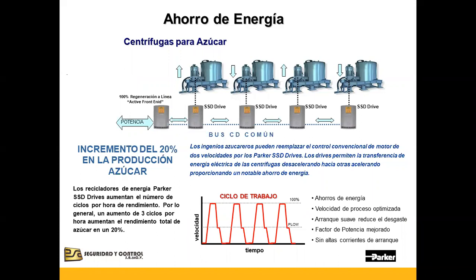Cuentan con el IGBT que se utiliza para el frenado dinámico y el circuito de detección de voltaje. Bastará con conectarle una resistencia de dos terminales al drive para agregar la función de frenado dinámico. No viene incluida en la compra, dado que quizás el 10% de las aplicaciones utiliza resistencia y el 90% no. Esa se compra por separado y también la venden ellos. En la configuración se indica si se quiere utilizar la resistencia.